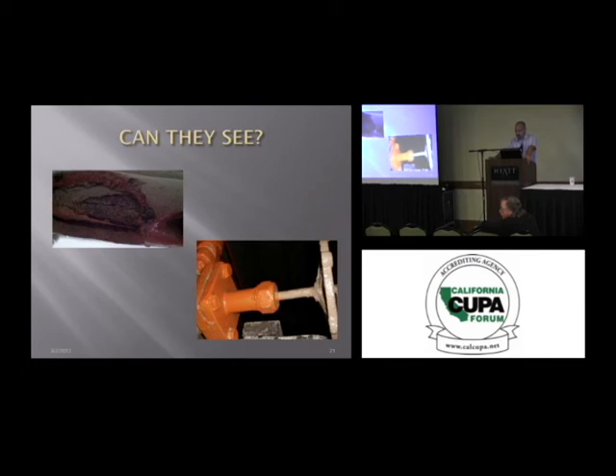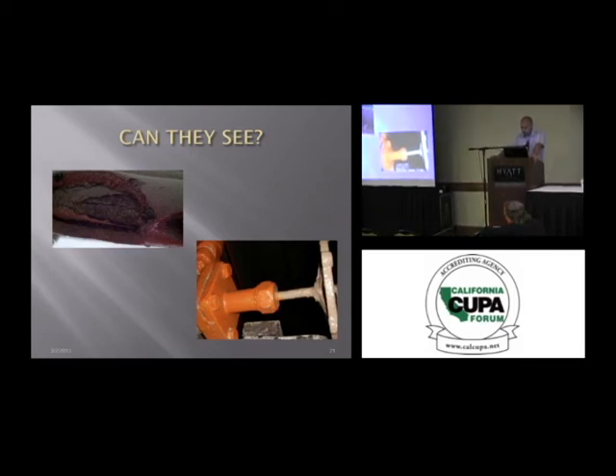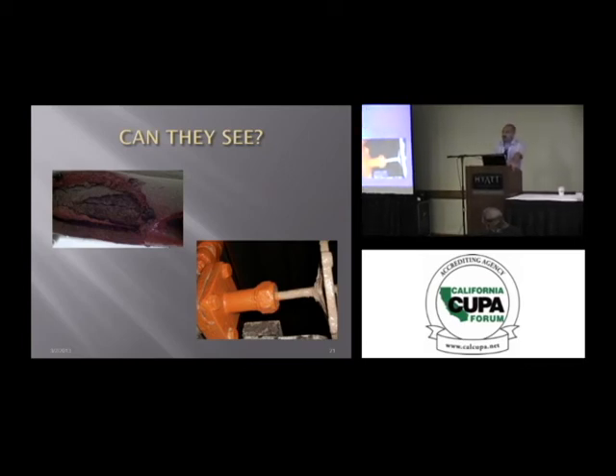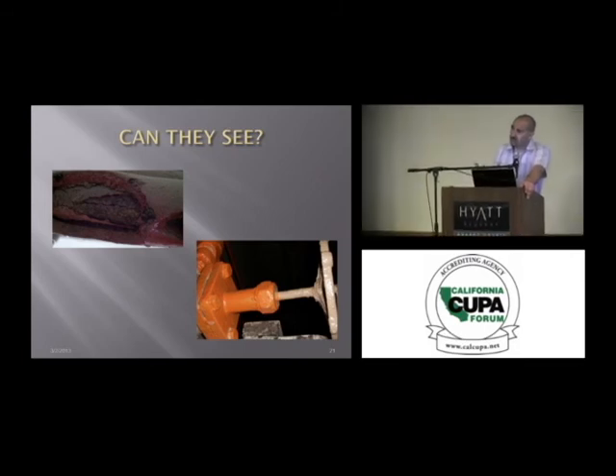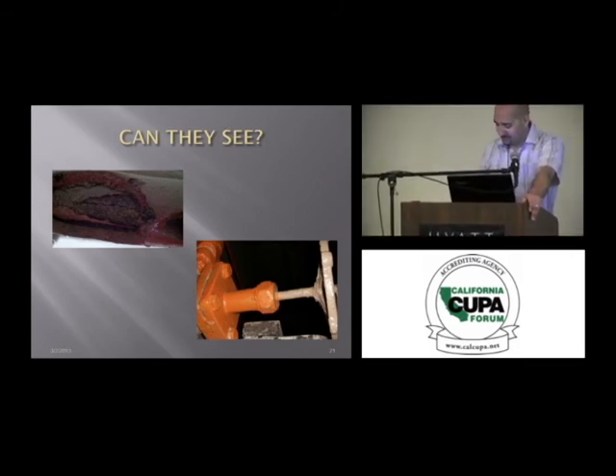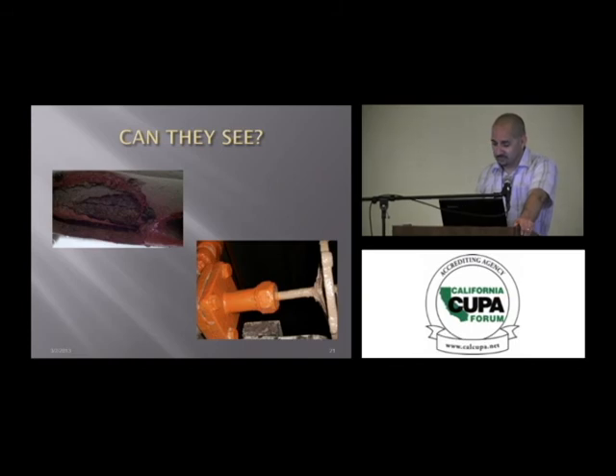And then once a year, maybe, if we're around condensers where there's overspray or there are some corrosion problems, like in a salt brine chiller room, etc. But as far as that, that's never been done. And if the valve is seized up when you need it to isolate, it's not going to be functional. You're going to have to do a large pump down and replace the pipe. And what do you think would happen if they turn that valve right now, to the valve packing? All the valve packing is going to get affected by the paint, and it's just going to leak from there. Yeah, and now you've got to go down to the next valve, isolate that one hopefully, pump that down and fix it. That's correct. Obvious here, just corrosion.